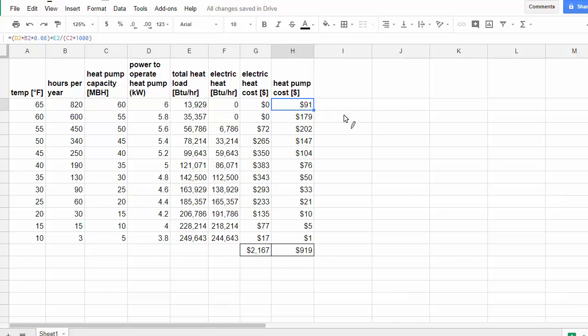like in this example we said it has to run for less than 15 minutes out of the hour, when it flipped the other way, they calculated a cost that had it running more than it possibly can. So for example here, they had it making up the capacity above and beyond the 50,000 BTUs per hour. They had it making up this extra 6,700 and running, let's say, an hour and 10 minutes within the hour. So this cost would go up. But that's physically impossible. It can't run more than 100% of the time.